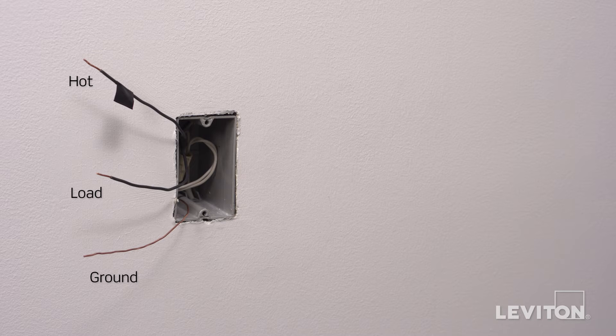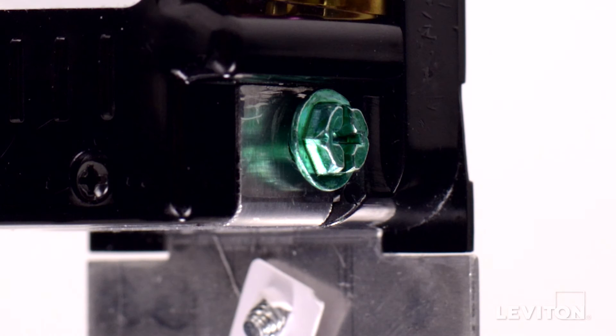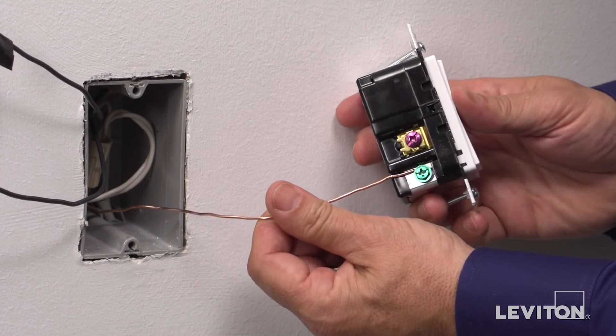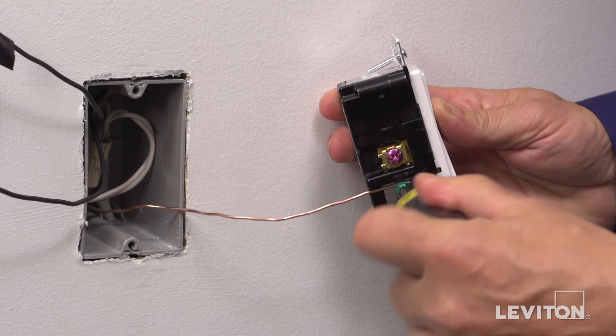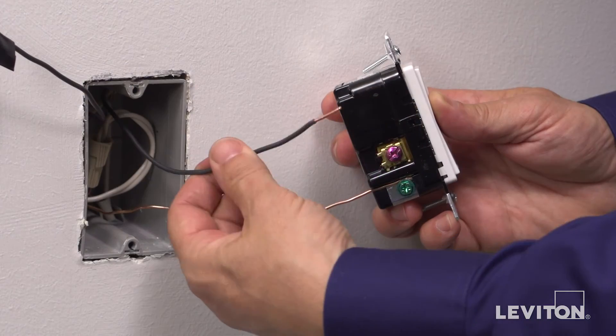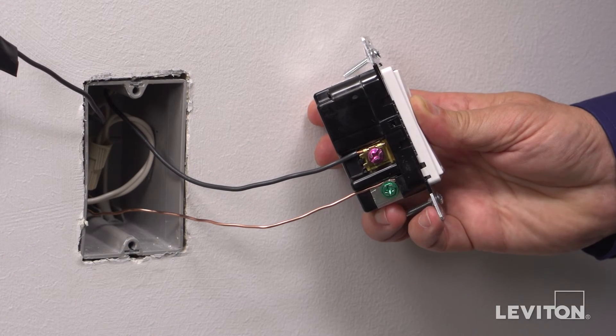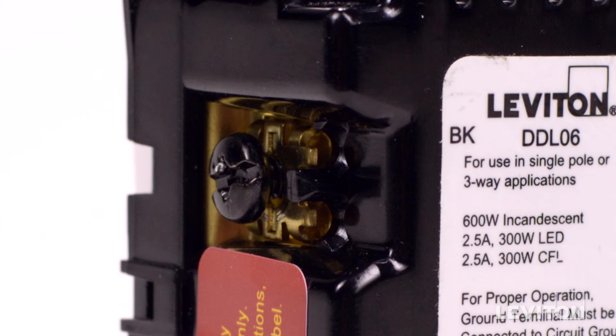Next, you need to be sure that the wires are prepared for installation. Start by making sure the wires are straight and stripped according to the strip gauge located on the back of the device. To wire, connect the green or bare copper wall box wire to the terminal screw marked GR. Connect the load wall box wire to the terminal screw marked LD.